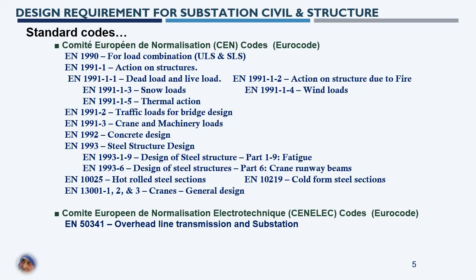EN 1991 Part 3 is for crane and machinery loads, required for designing foundations for cranes and machinery used during equipment installation at substations. EN 1992 and EN 1993 cover concrete and steel structure design respectively, with Part 1 Section 9 for fatigue load and Part 6 for crane runway beams. EN 10025 is for hot-rolled sections and EN 10219 is for cold-formed steel sections.